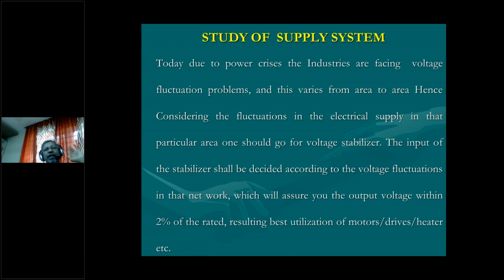Suppose there is a supply feeder change. Sometimes it happens in the substation due to some criticality or some power shortage, something like that. Suppose due to low voltage or overloading of that feeder, the substation has tripped that feeder and reshuffled it through a different feeder, meaning a different output, where you are getting better voltage, say 435 volts, something like that. In that case you may initially get 465 volts, and again equipment gets damaged.